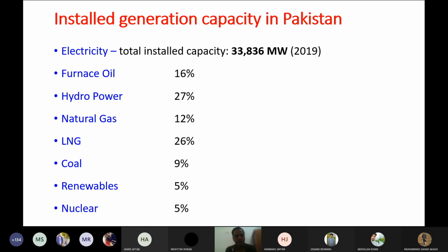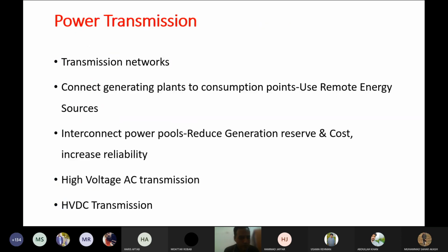We have two transmission voltages in Pakistan and one sub-transmission voltage. Write it down anywhere, because when I or somebody takes your viva, you will get confused otherwise. There are two primary transmission voltages in Pakistan: one is 220 kilovolt, or 220,000 volts, and the other is 500,000 volts, or 500 kilovolt. This is the primary transmission network of our country.